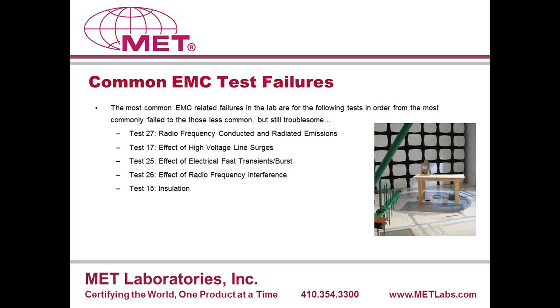Now, some of the common EMC test failures that we see here at MetLabs are, I've listed them in the order of most commonly failed tests. So the most common failure is on conducted and radiated emissions. As the name suggests, this is an emissions test where we perform emissions testing on your product. And the emissions testing is performed against the FCC Part 15 limits. But the important thing to note here is that this emissions test is performed against Class B limits, which is for a residential product. So even though your product may or may not be used in a residential environment, we are still required to test it against the Class B limits, which are more stringent than the Class A limits.